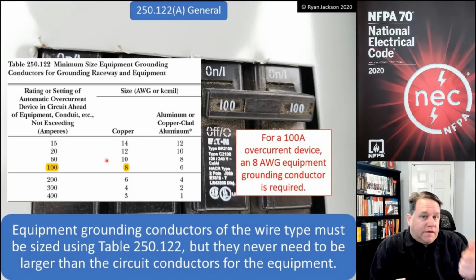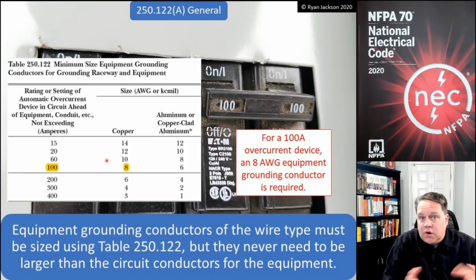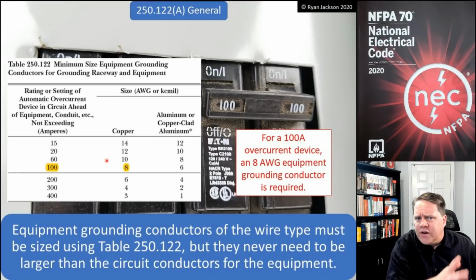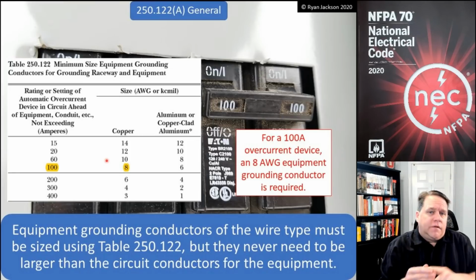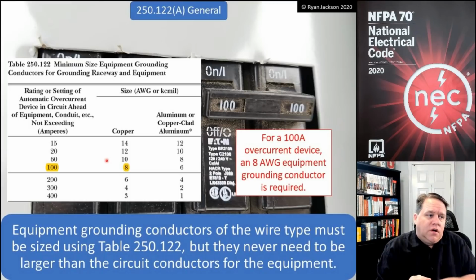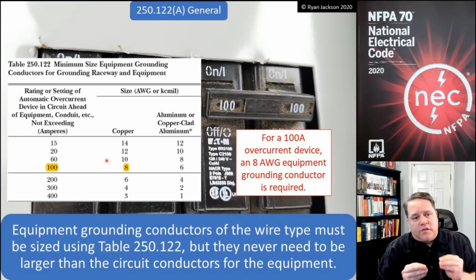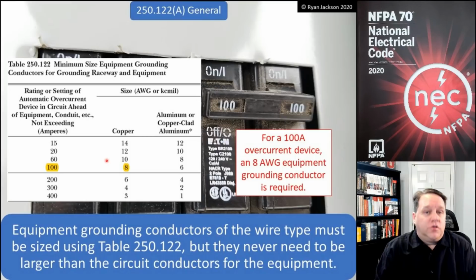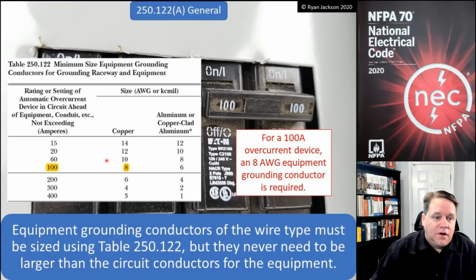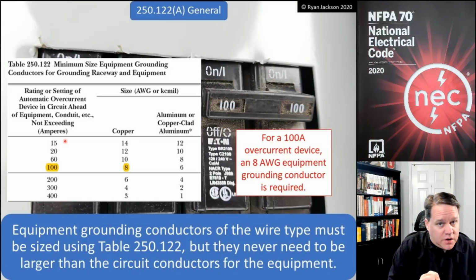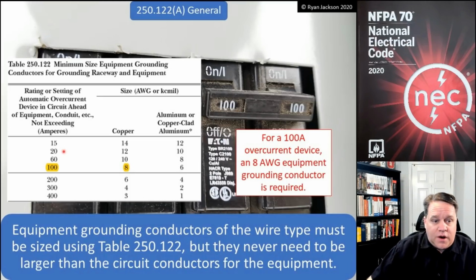That means that for a 15, 20, or 30 amp branch circuit, not talking about a motor or a feeder tap or anything, generally speaking, the equipment grounding conductor has to be the same size as the ungrounded conductor, right? For a 14 gauge, for a 15 amp circuit, I'm pulling 14 gauge ungrounded conductors, and I'm pulling a 14 gauge equipment grounding conductor. With a 20 amp, I'm using 12, 30 amp, I'm using 10.